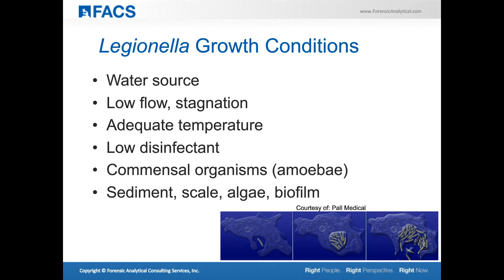Anywhere there's low disinfectant residual, such as low chlorine or whatever the municipality uses, can be associated with Legionella growth. The presence of commensal organisms like amoeba also matters. Legionella can actually utilize amoeba to proliferate and grow as a host, so the presence of those organisms increases a water system's susceptibility to growth. And then there's the presence of sediment, scale, algae, or other biofilms, which provide a food source for Legionella and a place for it to anchor and grow within a water system.